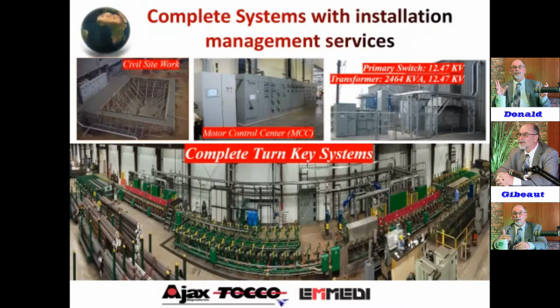You know, we can go higher, but that's not necessarily in our wheelhouse, what we like to provide. There are a lot of people. We're connecting to one right now that's 39 kV. They wanted us to connect to 138, but the 39 kV we settled on, and we're stepping it down to an end voltage of 480.